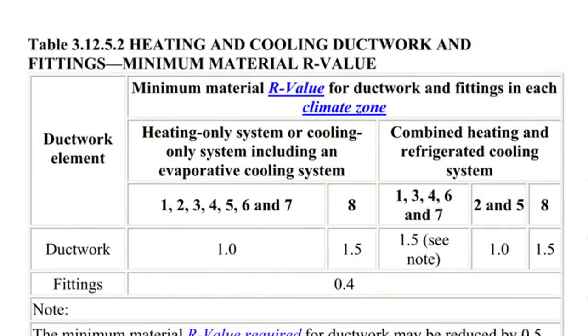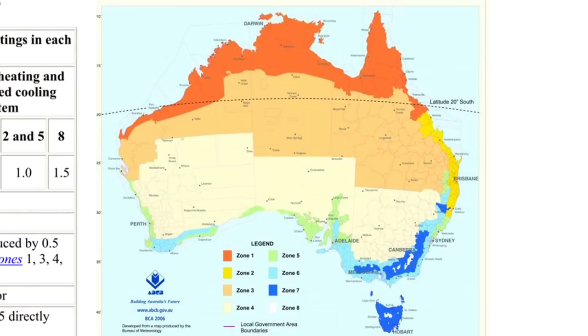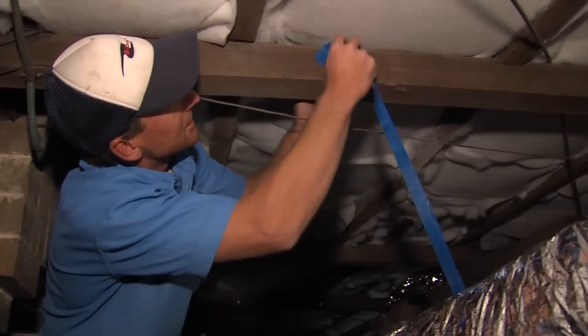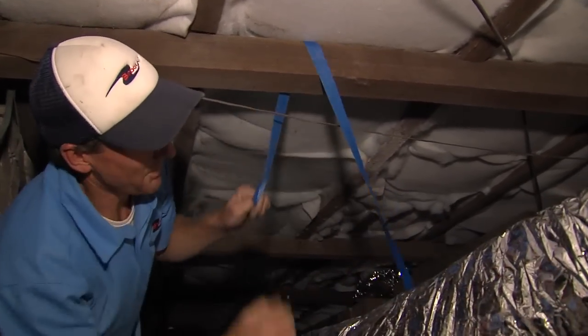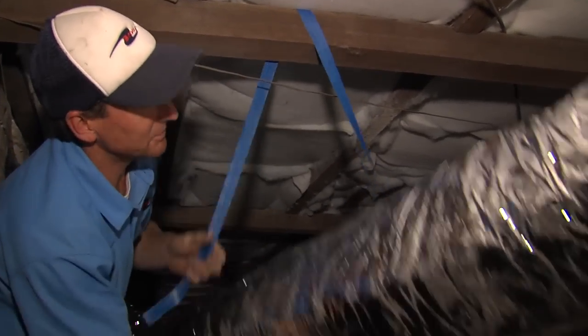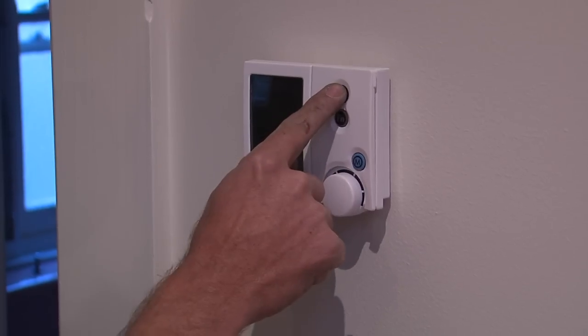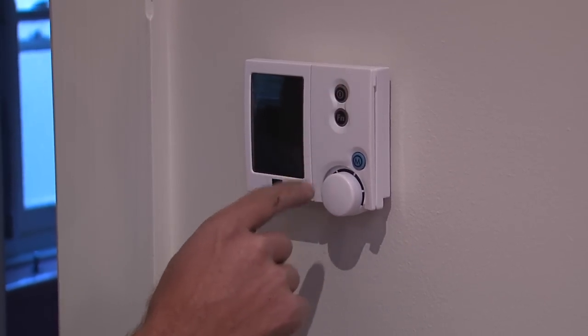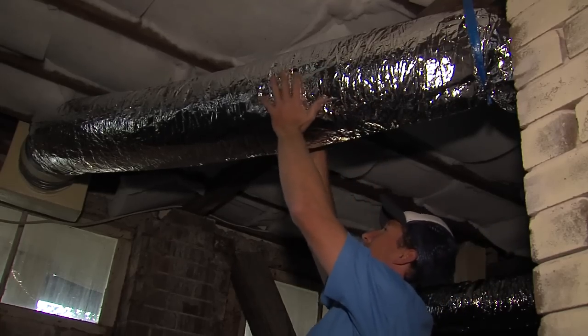Ducts must have the minimum insulation required for your climate zone — see our fact sheet for more info. Ducts are fragile, so try to locate them away from where they might be damaged, such as manholes. Once installed, turn the system on and check ducts for leaks.